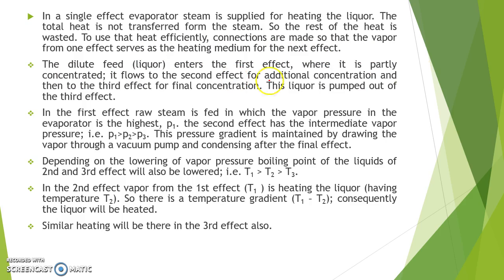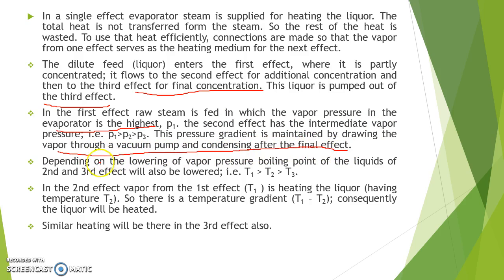The dilute feed enters the first effect where it is partly concentrated, flows to the second effect for additional concentration, and then to the third effect for final concentration. This liquor is pumped out of the third effect. In the first effect, raw steam is fed in, where the vapor pressure in the evaporator is the highest. The pressure gradient is maintained by drawing the vapor through a vacuum pump and condensing after the final effect. Depending upon the lowering of vapor pressure, the boiling point of liquids in the second and third effects will also be lowered.